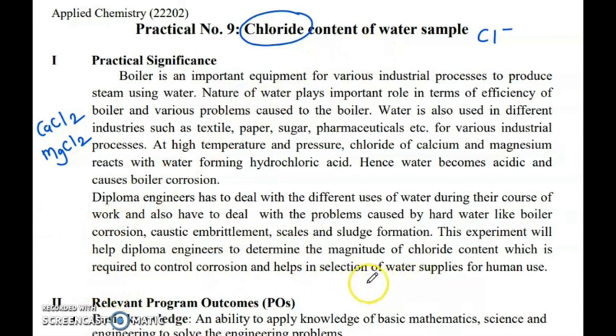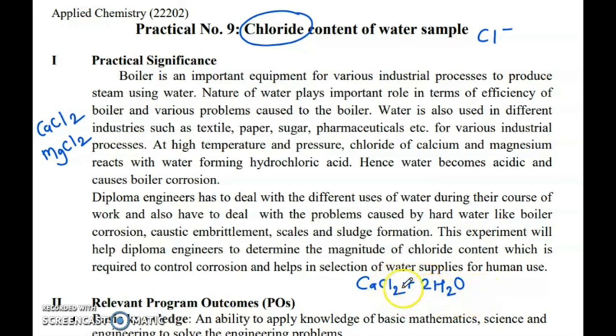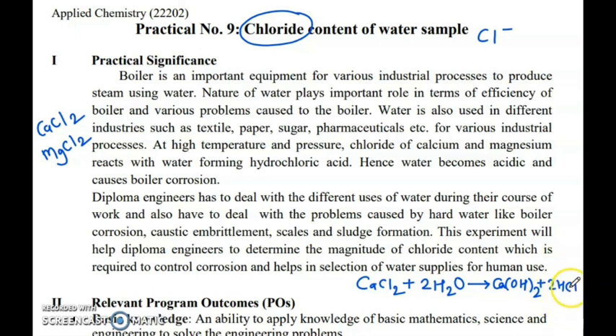Suppose if your water contains calcium chloride or magnesium chloride, at high temperature and pressure, that chloride reacts with the water. In a boiler, temperature and pressure both are high. At high temperature and pressure, that calcium chloride reacts with water and there is formation of calcium hydroxide: Ca(OH)₂ plus 2HCl is formed. HCl is nothing but hydrochloric acid, and in acidic media, rate of corrosion is higher. This hydrochloric acid is going to cause boiler corrosion.